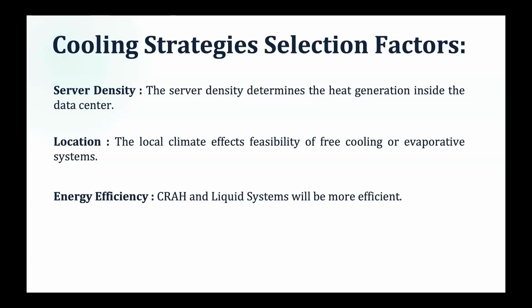The difference between a CRAC unit and a CRAH unit is the cooling medium. In a CRAH unit, chilled water is supplied to the heat exchangers, whereas CRAC units are direct expansion units. So when the server density is high and the heat load is high, chilled water is a much better option. So CRAH units are generally preferred, and liquid systems will be more efficient, depending again on whether the technology is available, whether it is affordable, and whether it can be implemented at that particular place for the given load.